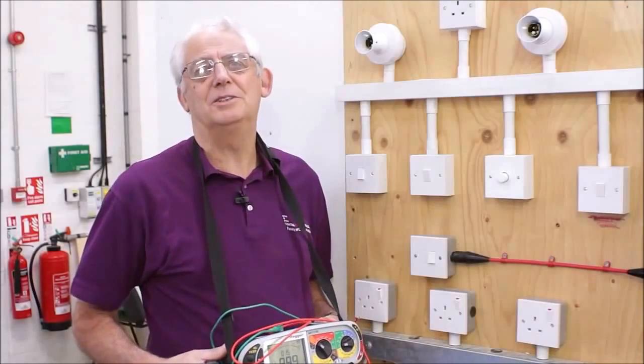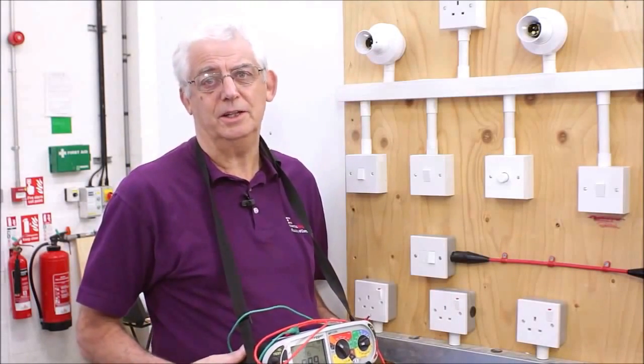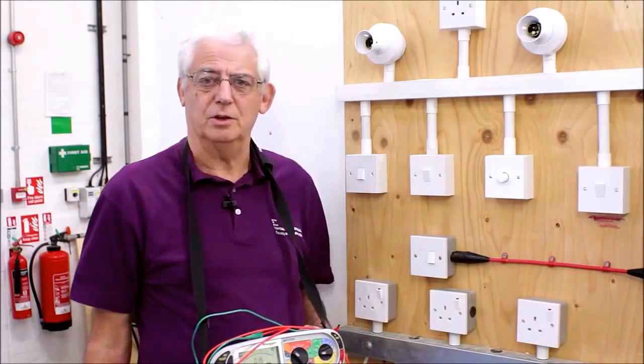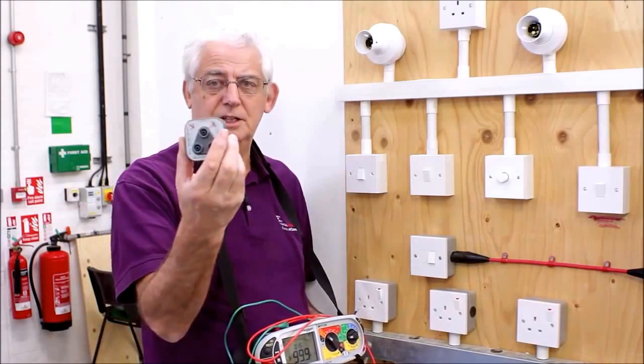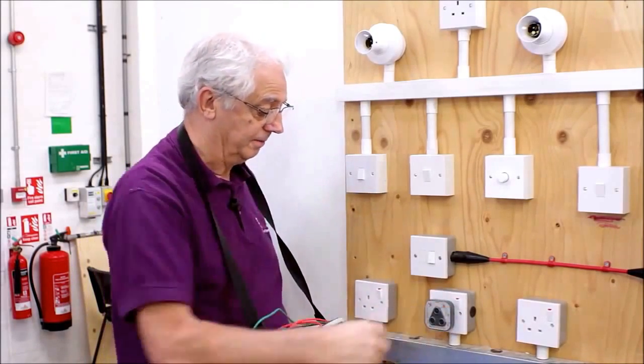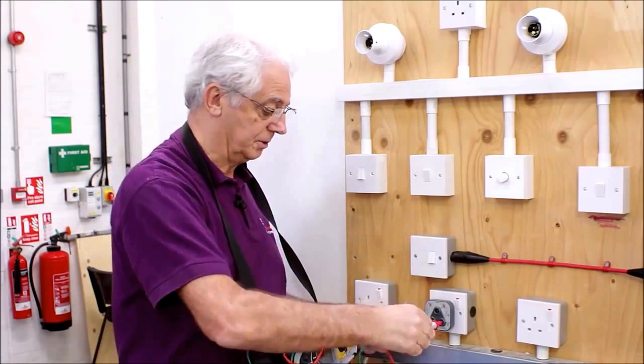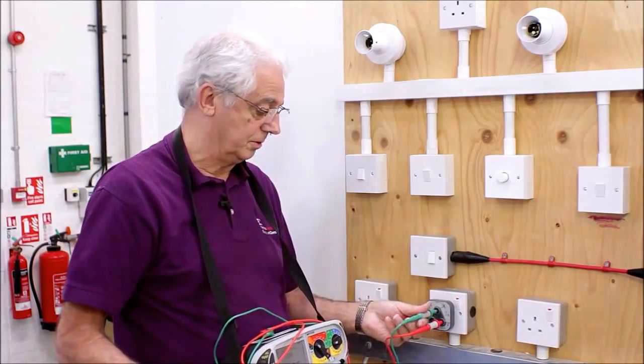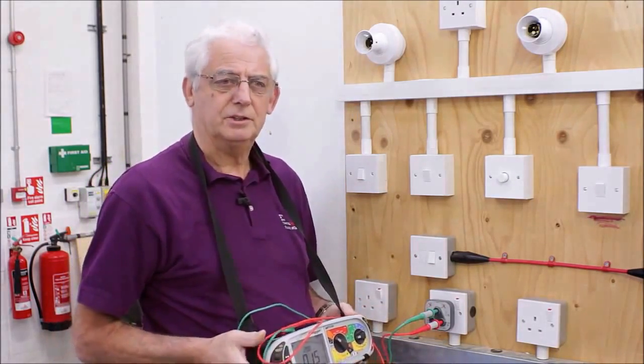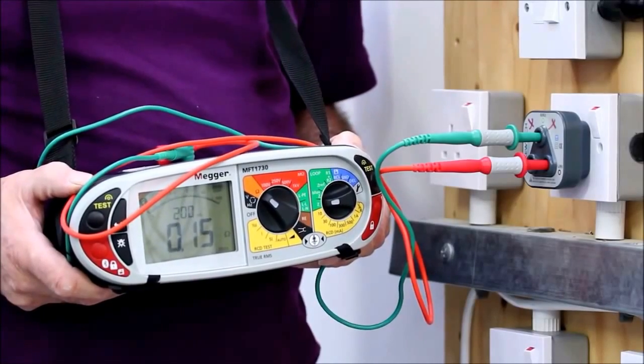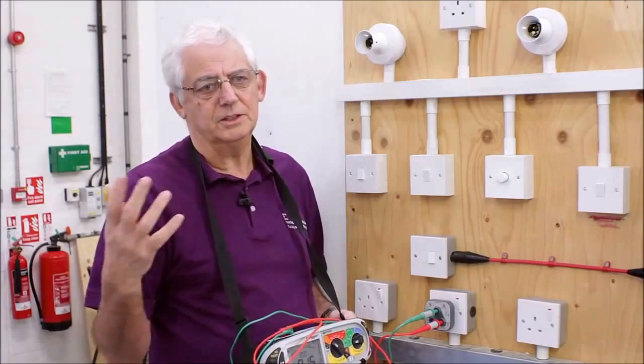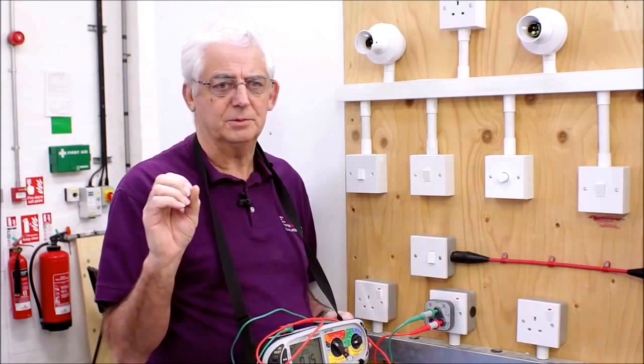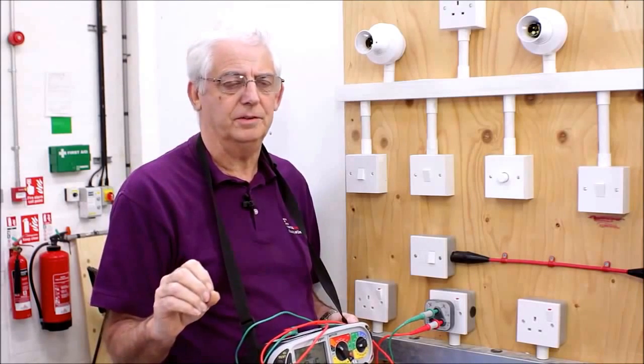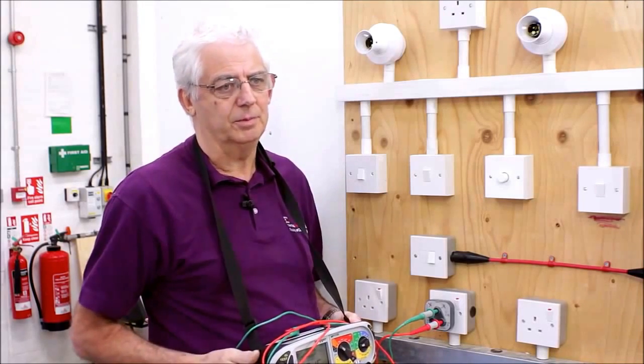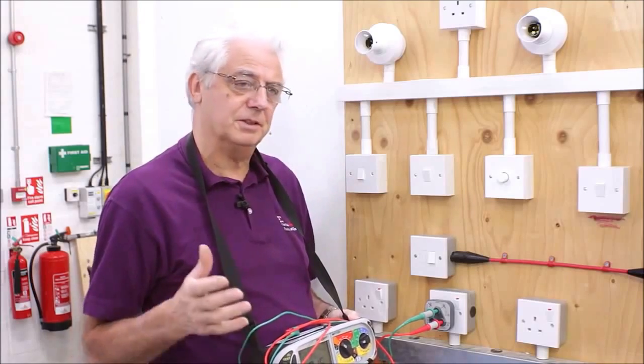I'm going to carry out a test between line and earth at each socket. Need to make sure the switch is turned on, of course, and I'm going to use a little test box. I'll plug that in, place my 2 probes between line and earth, and I should get a value of between 0.12 and 0.17. Providing it's within 0.05 of the original measurement, I haven't got a problem. And that should be the same for each socket outlet.